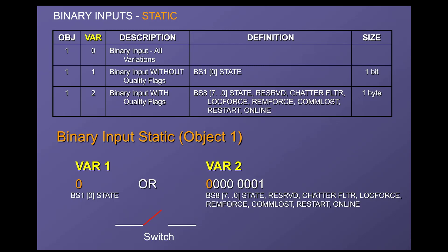When we look at how binary input data works, first we look at something called the static data type. In DNP3, static data refers to real-time data. Anytime we see 'static,' that's the name DNP3 gives to real-time data. Looking at static data points in object group 1 — all the static data types are in object group 1. Variation 0 is for master requests only. Variation 1 of object 1 is simply a status, a single bit, a 0 or 1 — just like in Modbus. That's all that's required: a single bit, either 0 or 1.